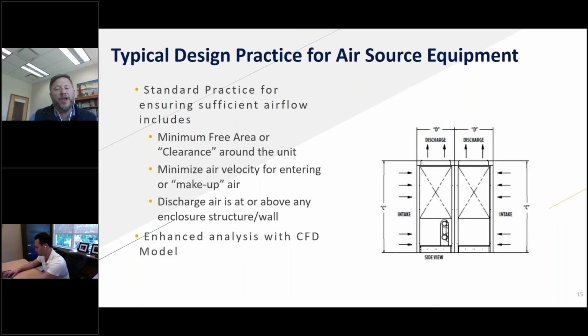Now, if we're installed on grade or on a concrete pad, you're not going to get any airflow coming up from underneath. But if we're up on dunnage, then there's a potential to bring air in there as well. When we do that, really what we're trying to do is reduce the velocity of the makeup air coming into the coil, so that the path of least resistance, the easiest way for us to get air, is from free air or fresh air versus having air come off the discharge of the unit and getting sucked back in, okay?